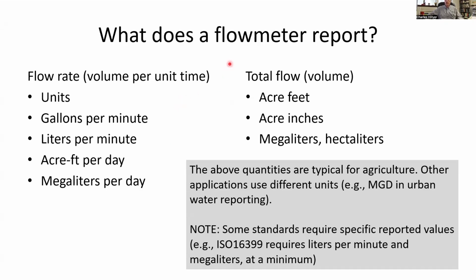Most of the meters that are available to you in MAGSA are going to have a totalizer in them of some kind. And so they can actually report two different numbers: the flow rate, which is the instantaneous flow rate, or the total volume that's flowed through the meter. That total volume that's flowed through the meter depends on some starting point where you start adding up the data. That's when aggregation becomes really important. Typically, if you don't change anything, that's going to be from when you first installed the data.